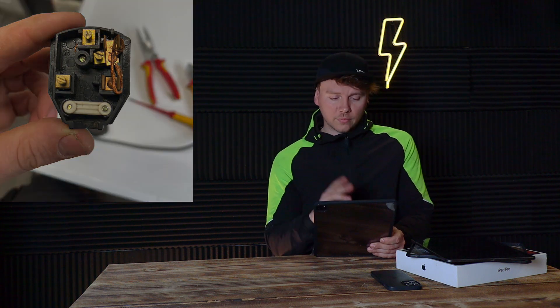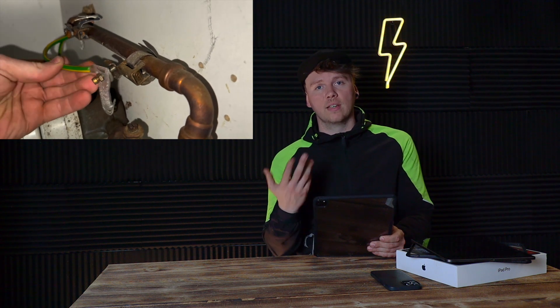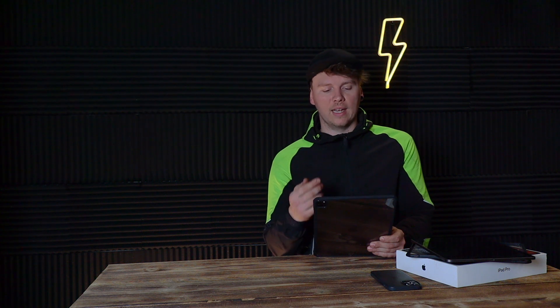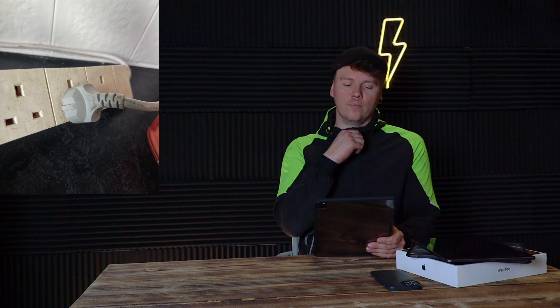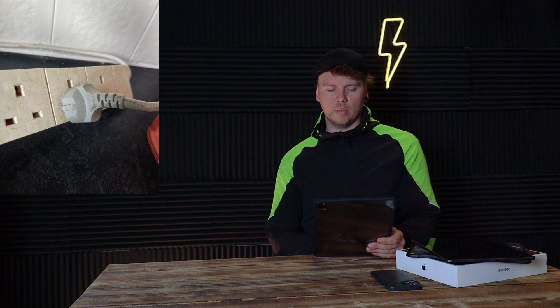There's also a little video from the same property where we started doing our Wander lead checks for bonding resistance — and you can see it wasn't bolted correctly, it was so loose it was flapping around in the wind, so we just had to re-correct that. Same property: there was also an extension lead on the kitchen side with a European socket plugged into it, which I just didn't like the look of.